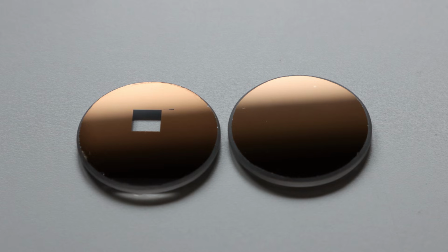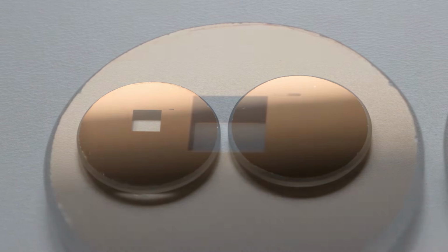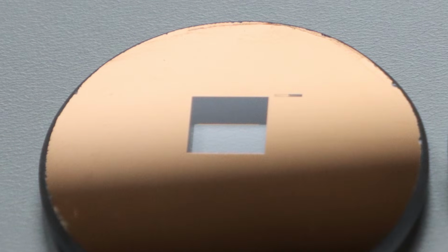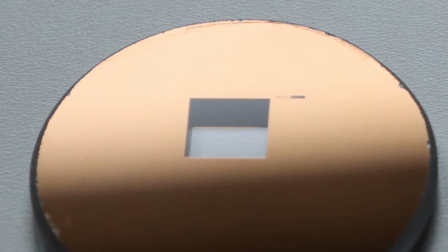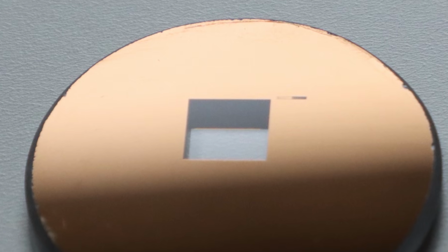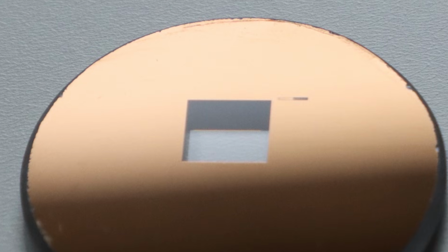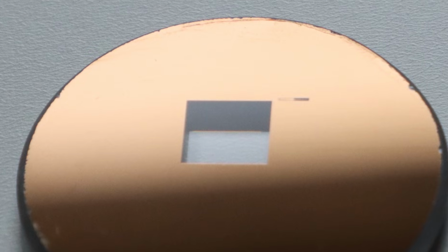And in both surfaces the chromium has about 25% reflectivity. An additional advantage of using a low reflectivity reference surface is that the sample also contains an air glass interface, which has even lower reflectivity, say around 4%. And for this reason, using a low reflectivity reference is also an advantage.